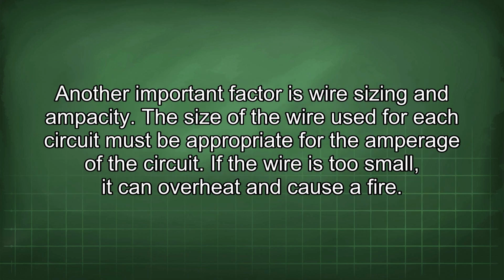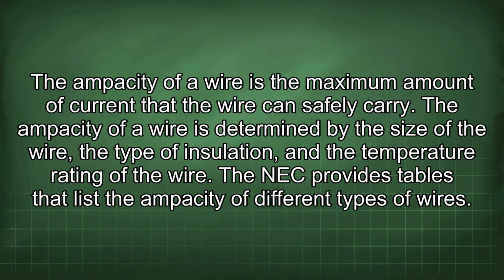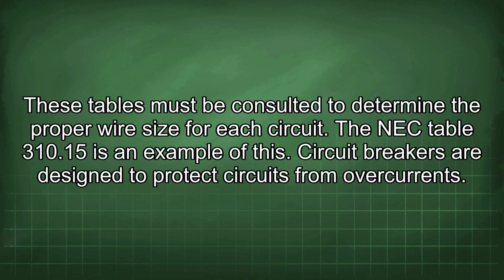Another important factor is wire sizing and ampacity. The size of the wire used for each circuit must be appropriate for the amperage of the circuit. If the wire is too small, it can overheat and cause a fire. The ampacity of a wire is the maximum amount of current that the wire can safely carry. The ampacity of a wire is determined by the size of the wire, the type of insulation, and the temperature rating of the wire. The NEC provides tables that list the ampacity of different types of wires. These tables must be consulted to determine the proper wire size for each circuit. The NEC Table 310.15 is an example of this.